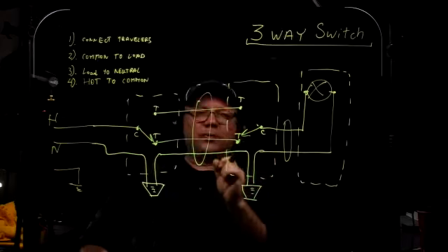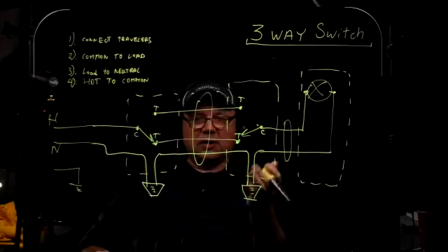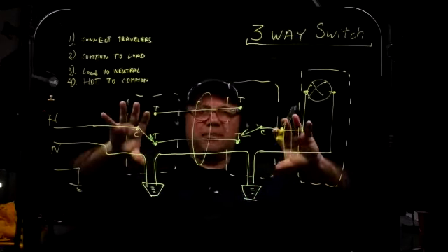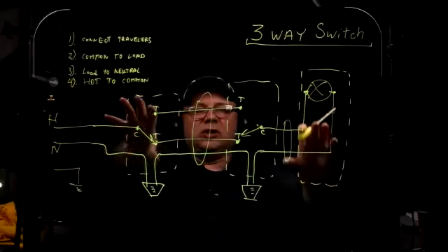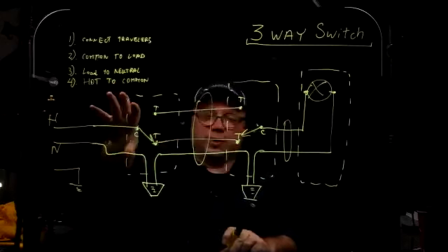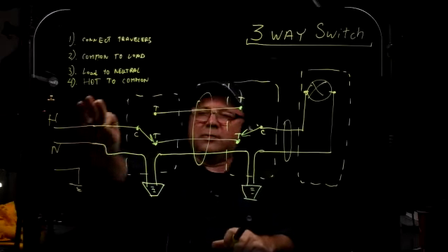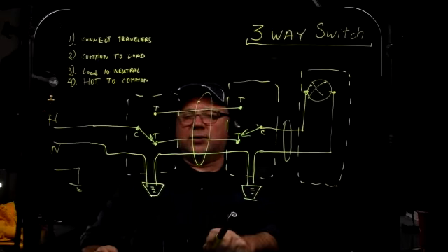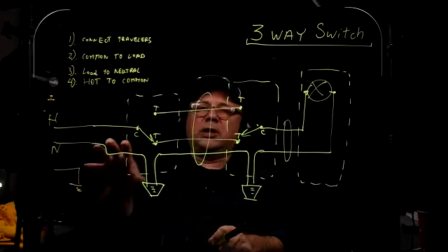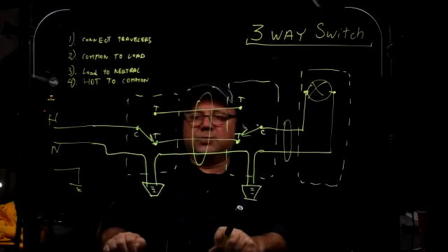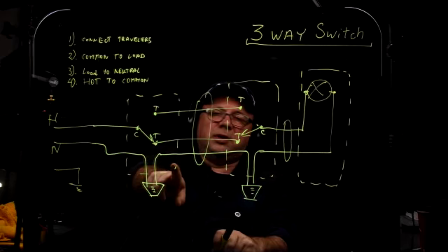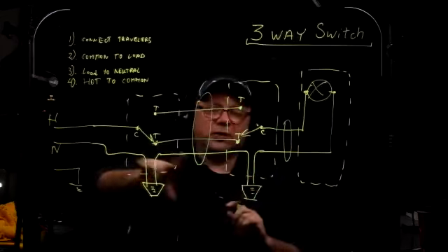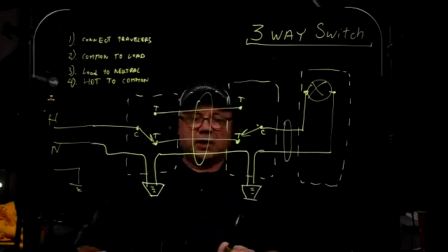Yes, that would be ground. It's a safety conductor. We don't have one here, but the situation would be if this was a PVC raceway system or conduit system, then we would have to pull another wire with it because the PVC does not conduct the electricity, so the ground cannot be carried through the metal parts of the whole system. And then yes, the PVC device boxes do have extra grounding or bonding terminals that you can connect the ground to. Okay.